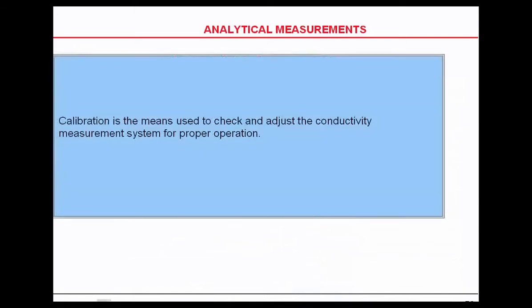Calibration is a means to check the conductivity measurement for proper calibration. It can be done two ways. If you want to check your instrument — if you're using a UDA or an APT — you simply use a resistor and then take a look at the reciprocal value. If you put a 10K resistor on an analyzer, it should read 100 microsiemens.